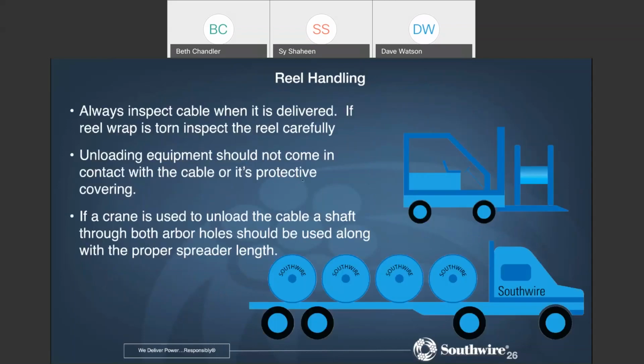When you get the reels, we always want you to be careful, always inspect the reels when they're delivered. If the on-reel wrap is torn, be careful. There's normally a wrapper on it. If there's a wrap, make sure you look at that cable before you take it off the truck and say, "Whoa, wait a second! The wrap is gouged, and I see the insulation or the jacket is gouged." Let us know. Unloading the equipment should not come in contact with the cable or its protective covering. This is how you want to unload it.